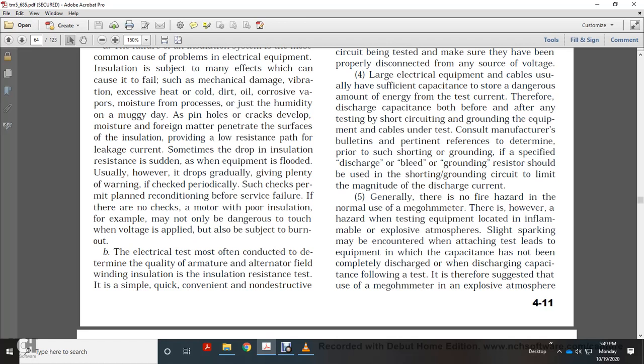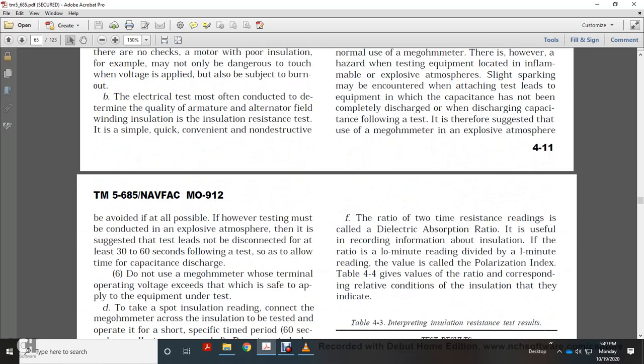Generally, there is no fire hazard when normally using the megohmmeter, but if the testing equipment is located where flammable material will explode in the atmosphere with a slight spark, take care when attaching the testing leads to equipment with capacitance that has not been completely discharged. Following a test, the capacitance must be discharged.